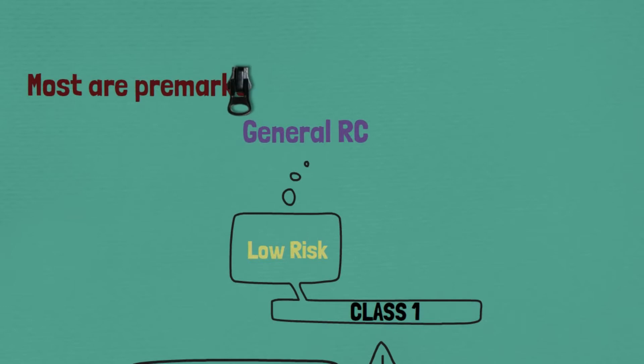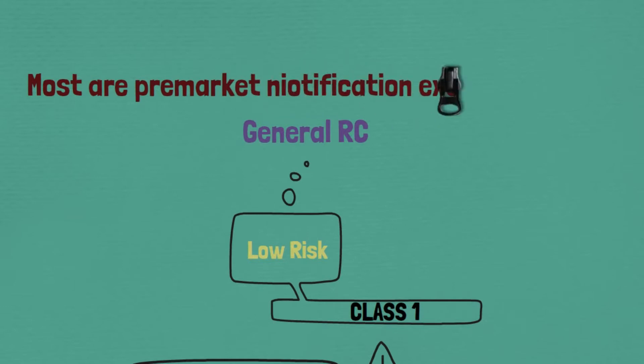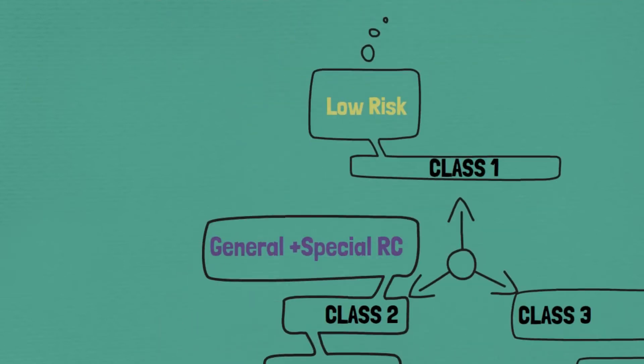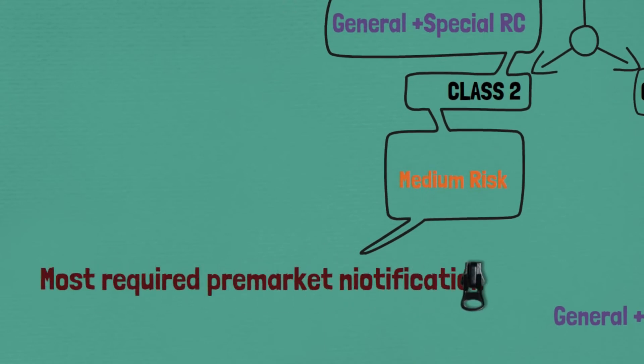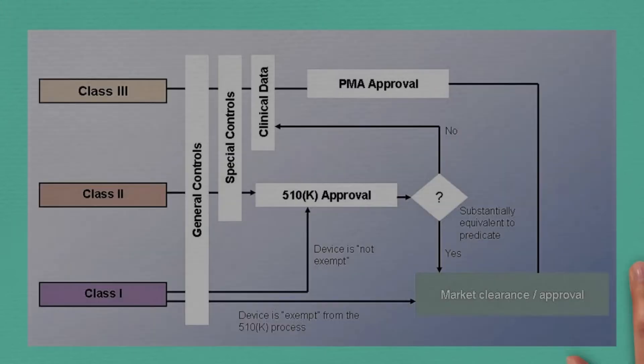Most Class 1 devices are exempt from pre-market notification, or 510k clearance. Pre-market notification is the submission made to the FDA to demonstrate that the device is safe and effective, or equivalent or better than an existing similar marketed device. Most Class 2 devices require pre-market notification, and most Class 3 devices require pre-market approval. Most Class 1 devices go directly to market release without pre-market notification, while the majority of Class 2 devices undergo pre-market notification before market release. Class 3 devices require clinical data to prove the device is safe and effective, and must also have pre-market approval before market release.